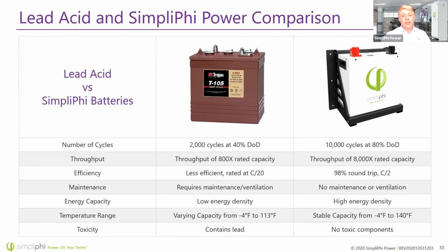As far as efficiency, you're going to get a higher efficiency, even at a higher discharge and charge rate, out of the Phi battery. You're going to get 98% round trip. Lead acid varies greatly, but I'd say maybe 85% at a higher discharge rate would be expected. There's no maintenance required for Phi batteries, no watering, no specific gravity checks or EQ charges, no sulfation to deal with, and no off-gassing. They don't need ventilation.